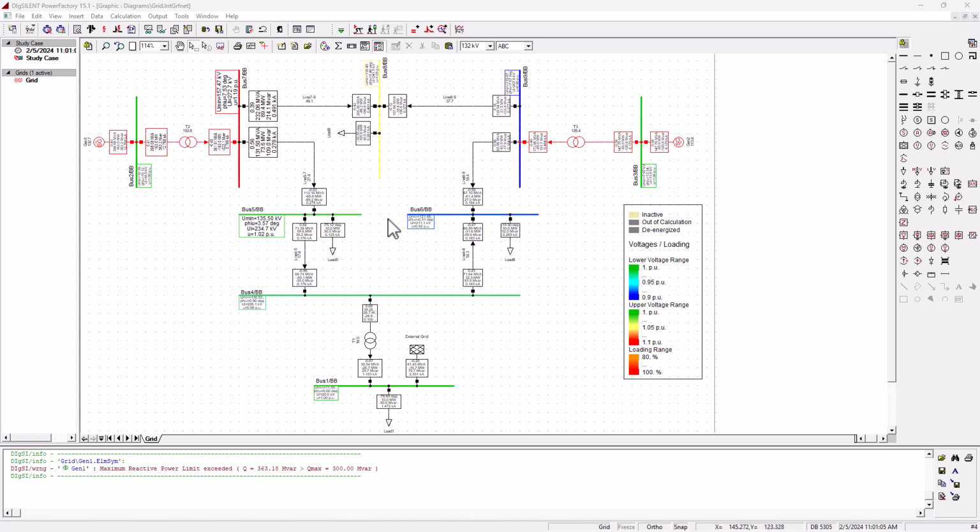Now, what's the solution here? Before we talk about the solution, a quick takeaway is that negative reactive power means the generator is absorbing reactive power, and positive reactive power on this side means it's injecting reactive power into the system. They're doing this all in the aim of trying to stabilize the system, even though in this particular scenario there is no coordination between these two generators. That's the problem that needs to be addressed.